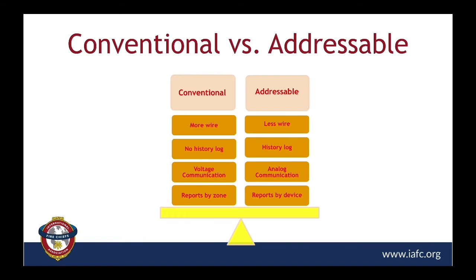So what's the balance between conventional and addressable systems? Here's a good little chart that gives you a general overview of how these things separate. Conventional is going to take more wires, as we pointed out. Addressable takes fewer wires; you can put everything on a pair of wires. There's also a history log on addressable, which we're going to get into in a minute on the intelligence side. Voltage communications versus analog communications are just different types of communications they go by. But the key one is the bottom line here: conventional reports by zone, addressable reports by device. If you don't remember anything else, addressable should equal individual device reporting. Conventional gives me a zone or an area of the building in which I have to look.